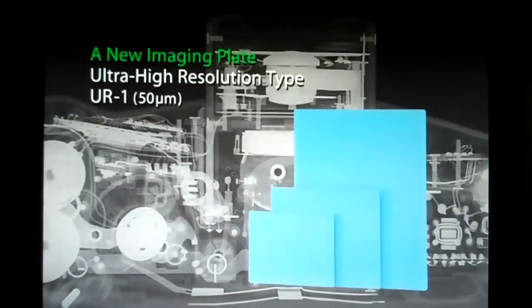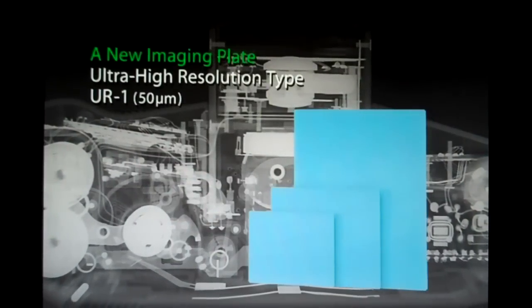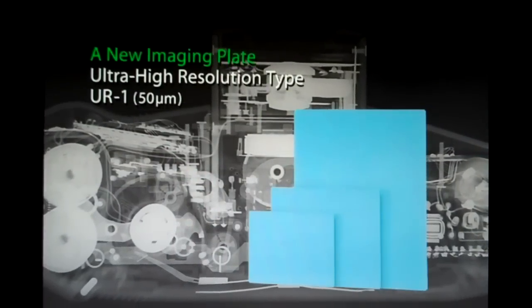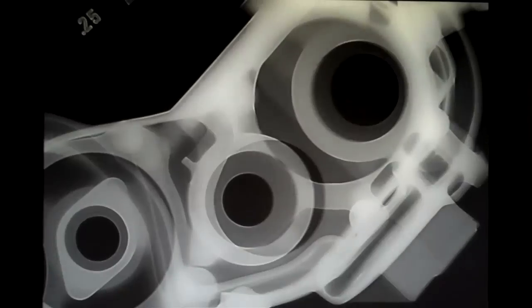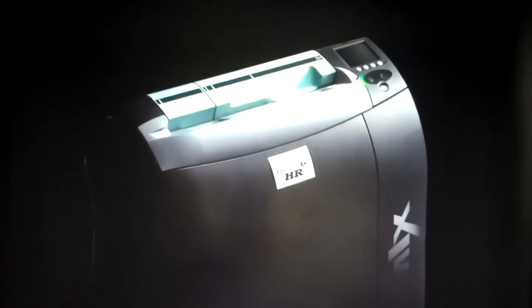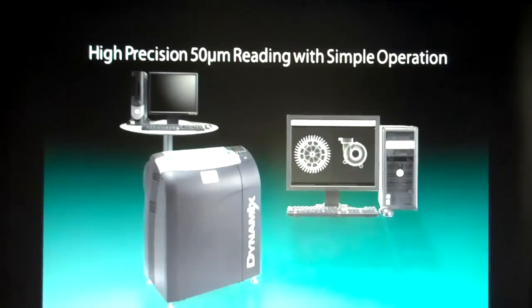Fujifilm, being at the forefront of CR technology, would also like to introduce a new imaging plate. By making the phosphor layer thinner and by tinting it, noise is controlled, giving you clearer images. As a result of these two developments, namely in the system and the imaging plate, the Dynamix HR is able to display high-resolution images of 50 micrometers with very simple operation.